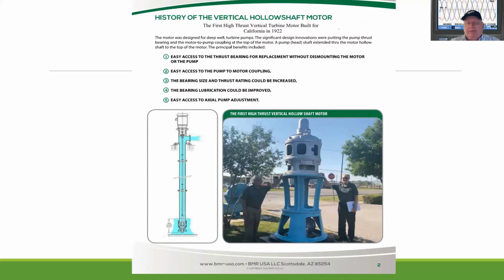This happens to be one of the first vertical hollow shaft motors ever designed and built. There's really a uniqueness to this, and what they did it for is efficiency, because everything before used to be belt drive, which meant you had 3 to 5% loss in your belts, or it had to be a gearhead with a horizontal motor driving the gearhead, and then again you had losses. Well, they designed the motor so they could drop it right on the top of the pump, brought the pump shaft up, put the thrust bearings on the top, and allowed that motor to carry the thrust, and then there were literally no losses between it and the turbine pump. So the motor ends up being much more efficient.